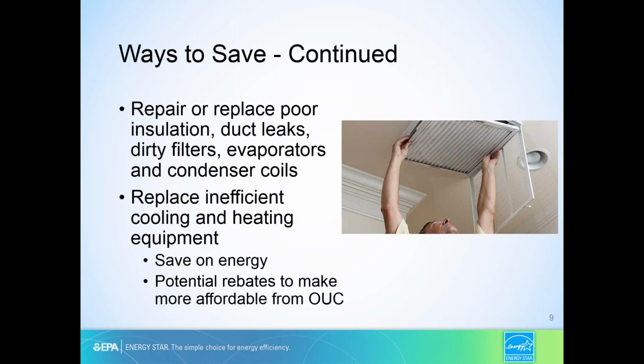We uncovered several parts of our buildings that hadn't been touched or had been kind of ignored over the years, and we were able to save upwards of 25 to 27% in a lot of facilities just by turning things off, putting buildings on controls, changing out the thermostats to smart thermostats, and replacing and repairing some ductwork that was allowing uncontrolled airflow through the spaces. You really want to be able to cool the places where you have the load, and not push cold air through your attic or plenum space where nobody is occupying the space.